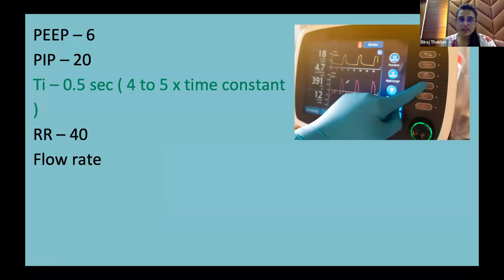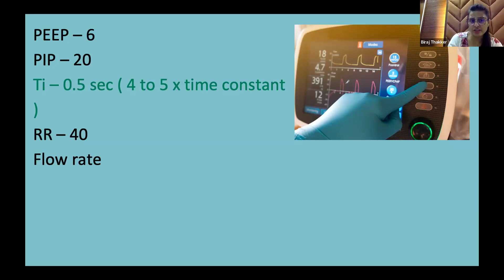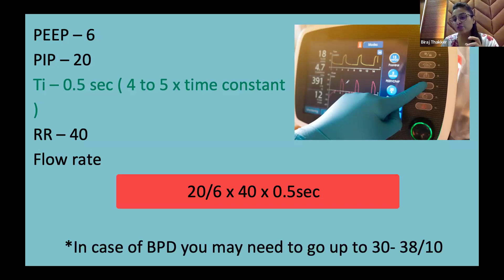It is 0.5 seconds. Why? Because we have anatomical dead space here. There you have intubated, and the ET is directly at the lung level, the carina level. So the I time we usually set is 3 times the time constant, that is somewhere around 0.35 to 0.4. But here we set the I time on the higher side because we are on non-invasive support. So that is 5 times the time constant, that is 0.5 seconds. So start with 20/6, rate 40 and 0.5 seconds. Sometimes in case of BPD, though I have not gone this high ever, you may require to go as high as 30 to 38 of PIP and 10 of PEEP.